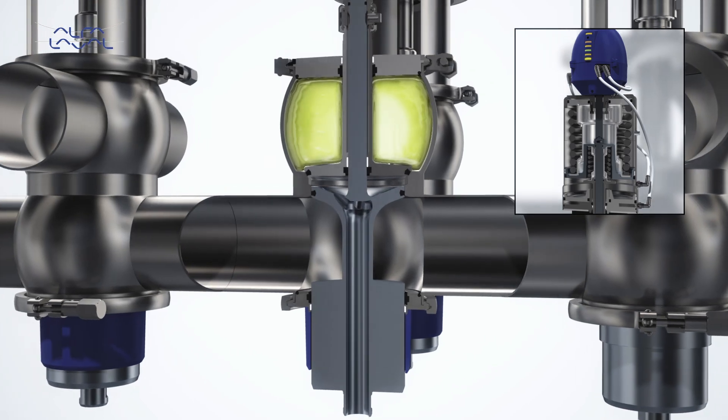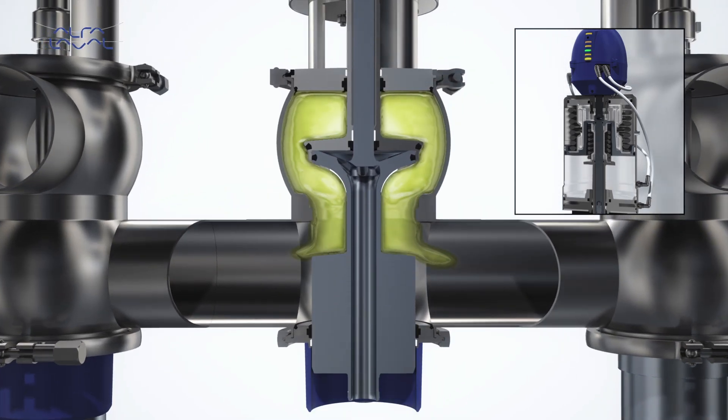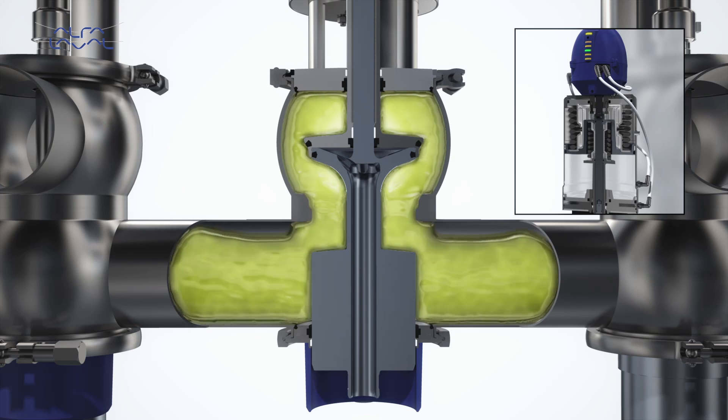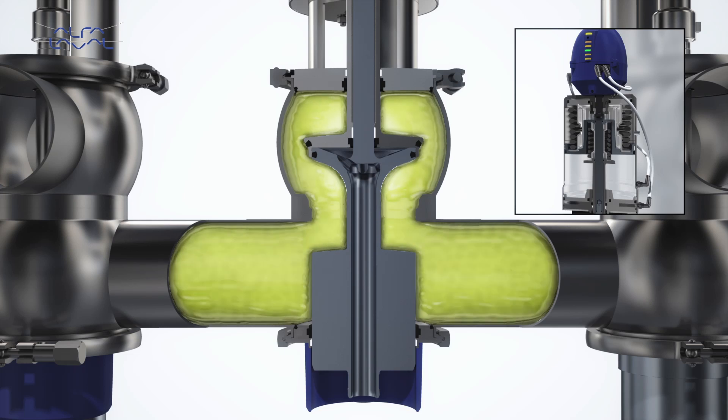Opening the valve is a two-step movement. First, the actuator retracts the lower plug, pulling it up into the upper plug. Then, it continues to lift both plugs into the fully open position.